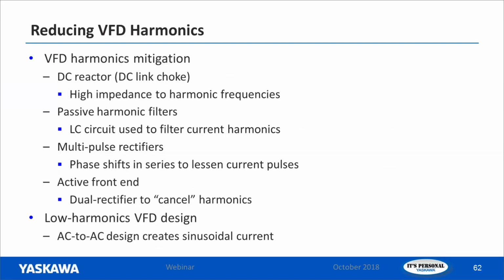So let's take a look at mitigation. We've covered harmonics and harmonic distortion, what it is, but now what can we do about it? We're going to look at a few of those methods. One would be a DC reactor or a DC link choke, which adds impedance to harmonic frequencies. Passive harmonic trap filters. Multi-pulse rectifier inputs, like a 12-pulse or 18-pulse input. And then there are active front-end VFDs, and low harmonics VFD design, which would be an AC to AC design, creating sinusoidal current. It's kind of skipping the whole DC bus phase of the situation.